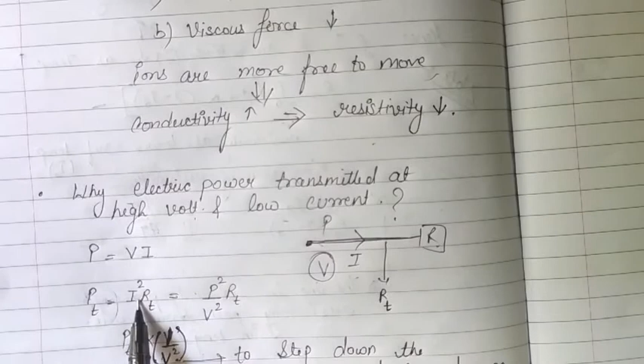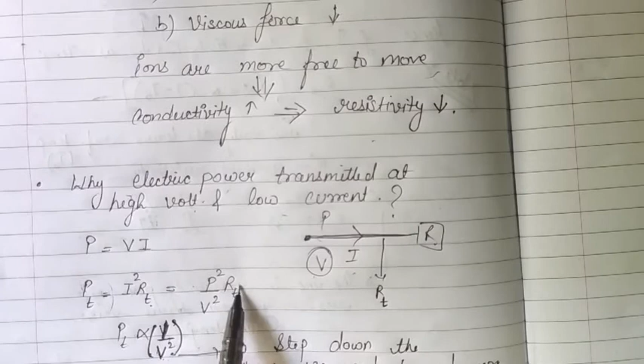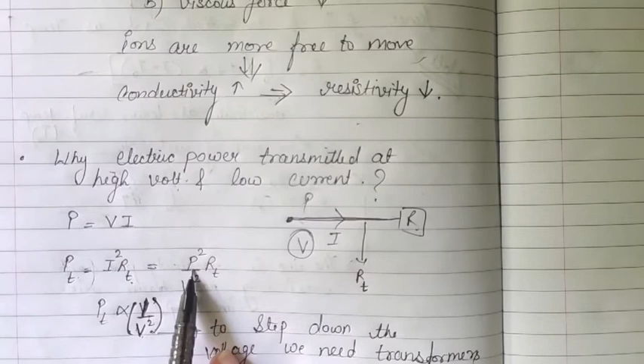So the reason is, the power consumed is VI, and the power wasted in the cable is I squared R_T. If I substitute the value of I, it will be P squared upon V squared R_T. That means the power wasted in the cable is inversely proportional to the square of voltage. If I keep V minimum, then I get maximum loss, but that is not the task. We want to minimize the power loss in the transmitting wire. So to minimize this, we need high voltage.